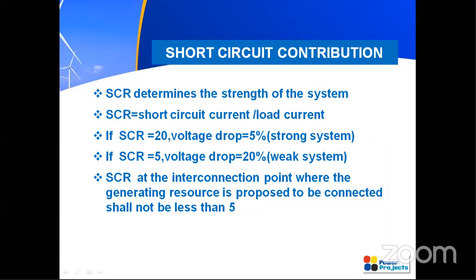So this voltage drop and the short circuit contribution are related one way or the other. I will tell you in detail in this slide. The short circuit ratio determines the strength of the system. If the short circuit ratio is of a greater value, it is a strong system. If the short circuit ratio is of lesser value, then it is a weak system. I will tell you how we name it as a strong or weak system.